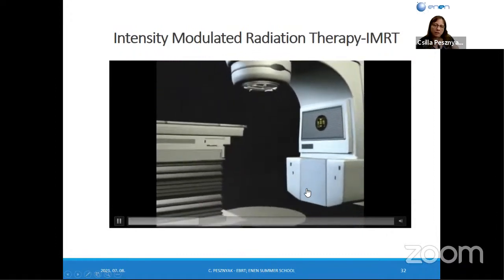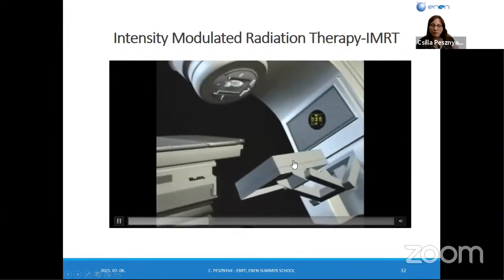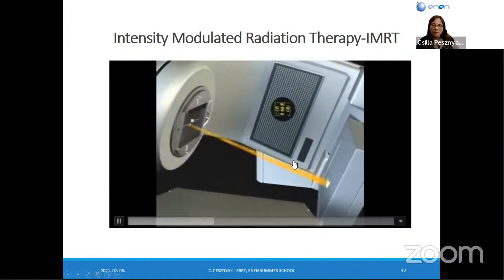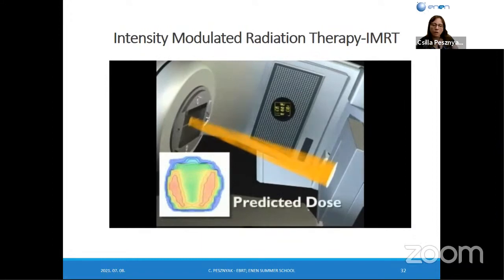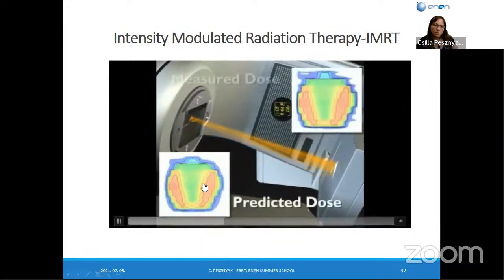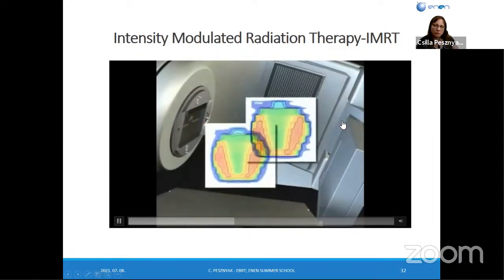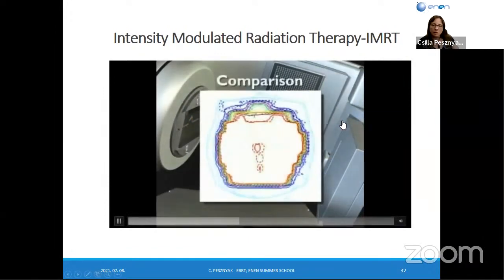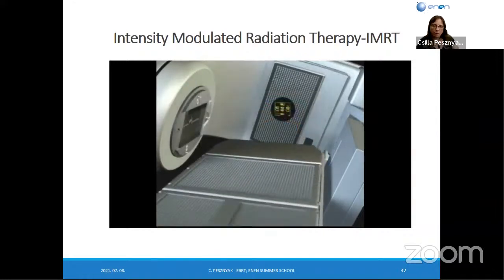All our accelerators are equipped with the portal imaging device. It is an amorphous silicon device, and it is useful for the measurement of the dose, because we have a predicted dose from the treatment planning system and we measure it, and if it matches at a minimum of 95%, after that we can irradiate the patient.